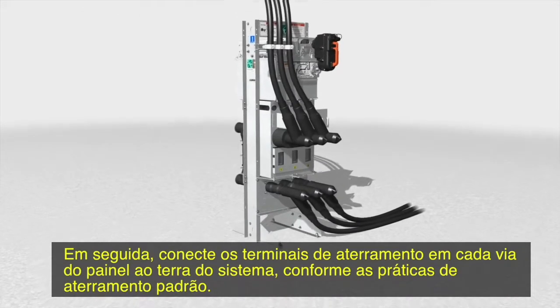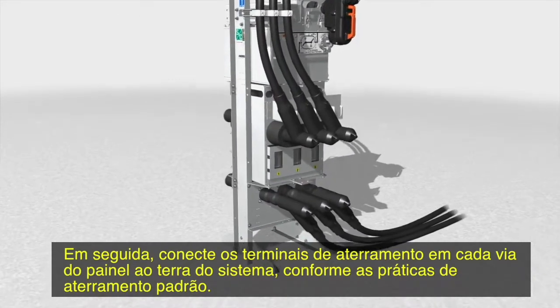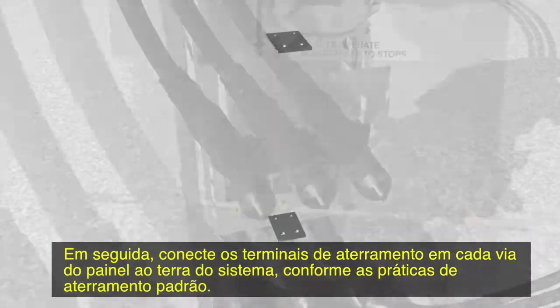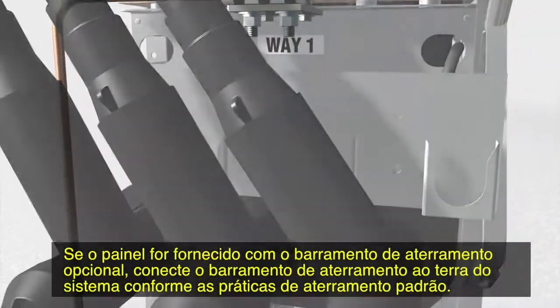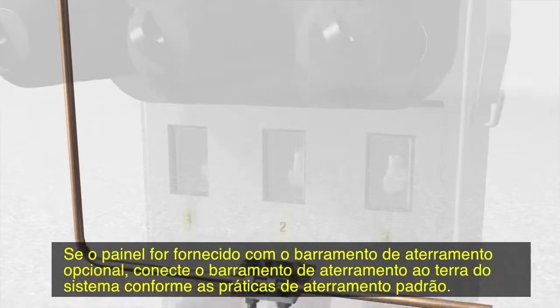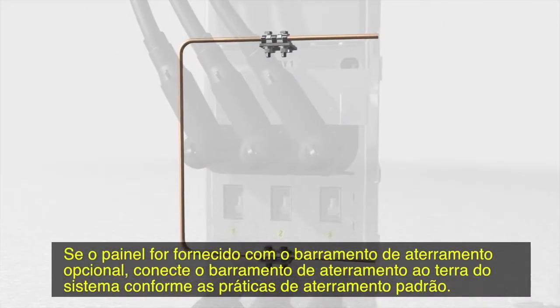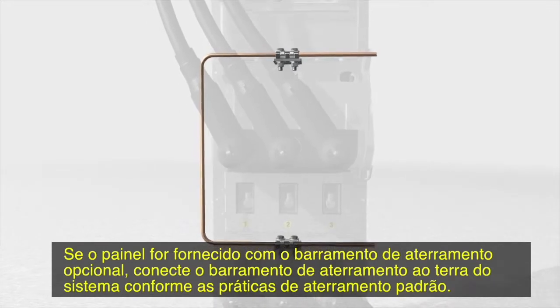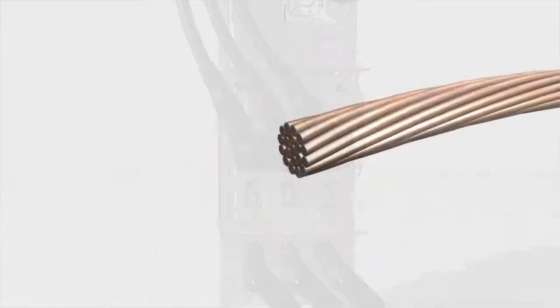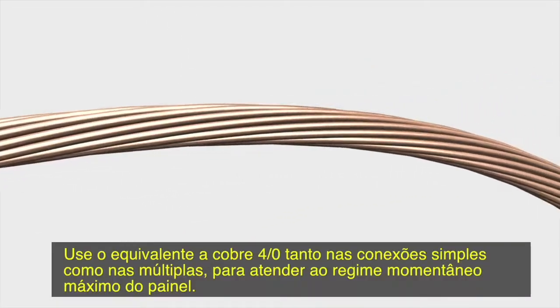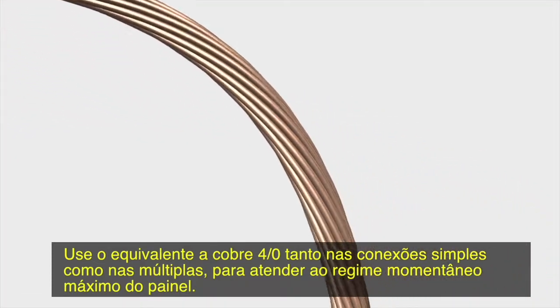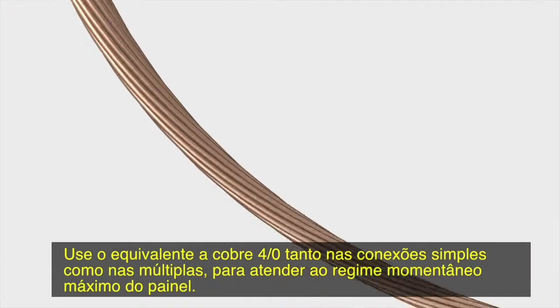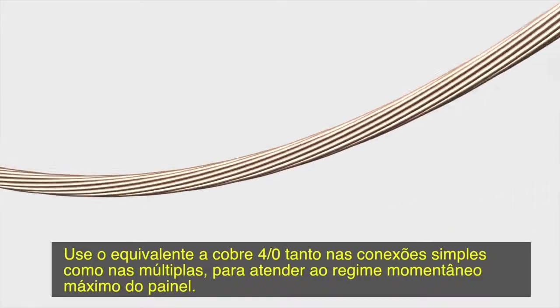Next, connect the ground pads on each way of the switchgear to the system ground in accordance with your standard grounding practice. If the switchgear is furnished with the optional ground bus, connect the ground bus to the system ground in accordance with your standard grounding practice. Use the equivalent of 4/0 copper in either a single or multiple connection to realize the maximum momentary rating of the switchgear.